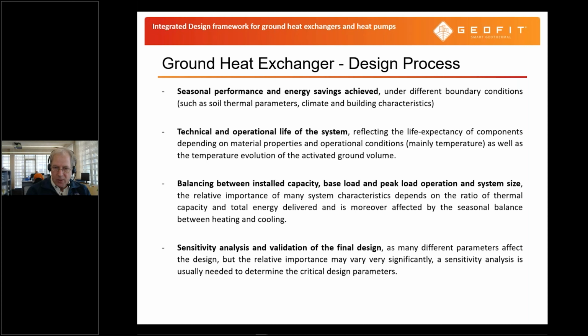We also want to take a look at balancing between the installed capacity and the energy that we want to take out of the ground. If you have a low energy load with a high capacity, obviously this capacity will be very important in the design. But if we take out the same amount of energy with a smaller capacity, the whole design changes, and we can achieve this with a smaller ground heat exchanger.